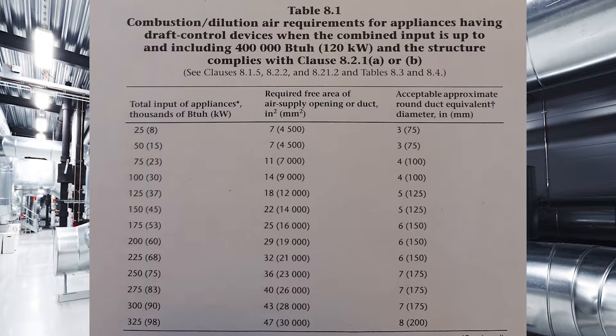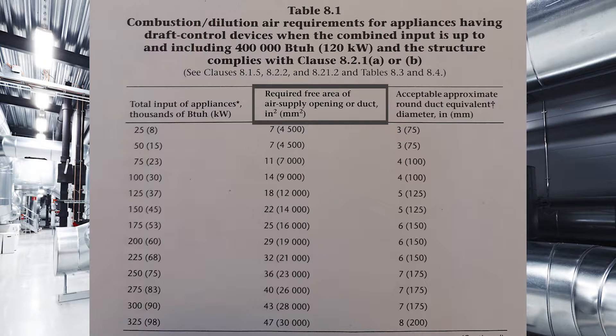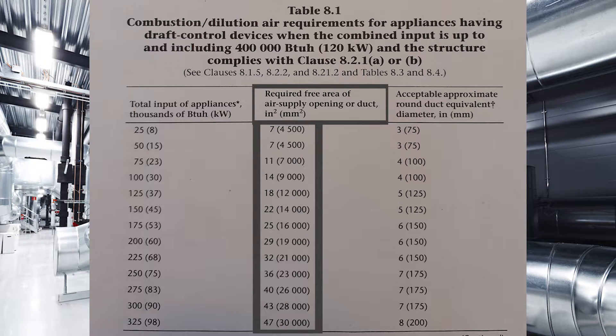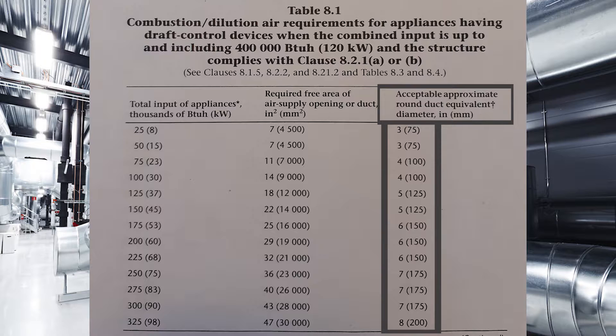Note how both tables are laid out. The far left column shows total input of appliances in thousands of BTUs per hour (or kilowatts). The middle column shows required free area of the air supply opening or duct in inches squared or millimeters squared. The next column shows acceptable approximate round duct equivalent diameter in millimeters and inches. For these videos I'm going to be using BTUs and inches, but the table works the same way with kilowatts and millimeters.